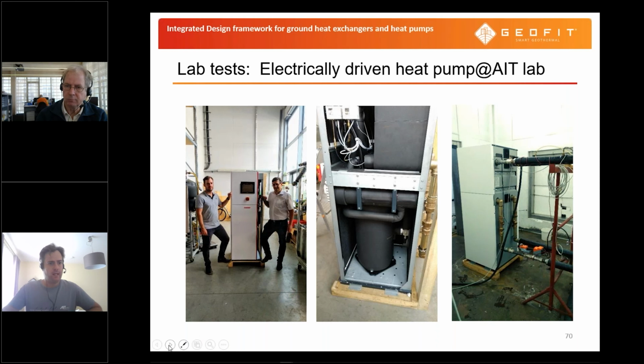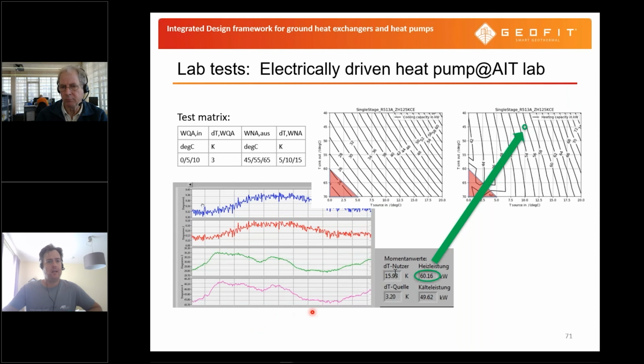So putting that heat pump to the test stand, the campaign was not completely a testing following the standards, the norm, but it was a testing following the conditions we foresee for the pilots, and we compared those testing points with our modeling, and we saw a good agreement, which we took further for the system simulations. Yeah, so we have a tested heat pump, and we have a validated model of that prototype.